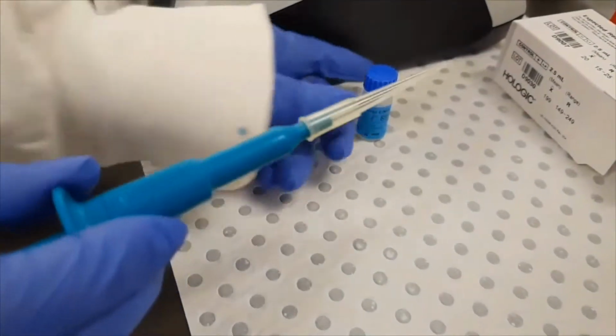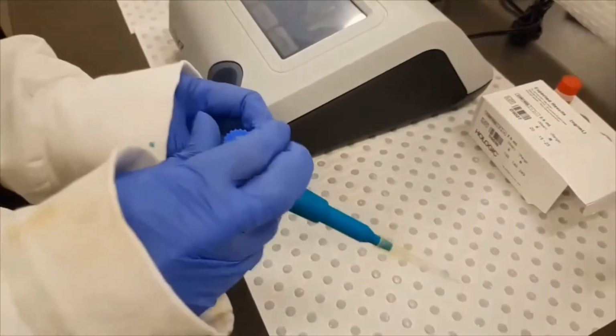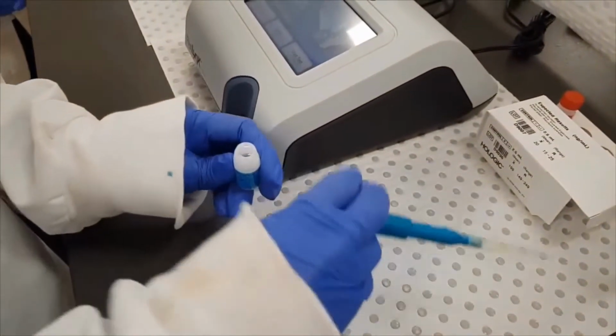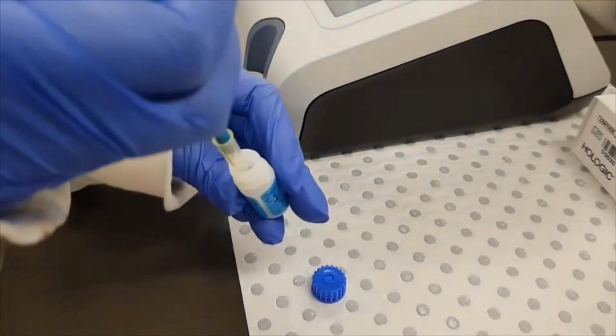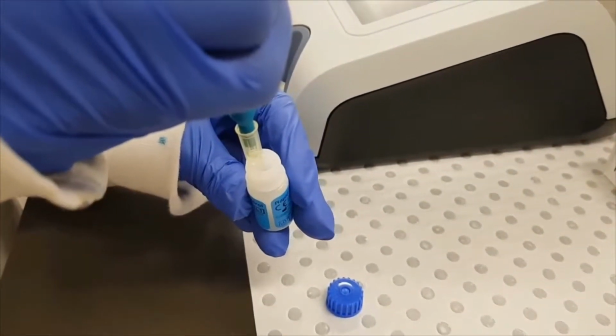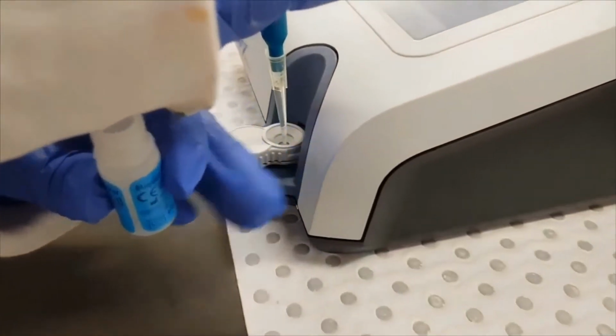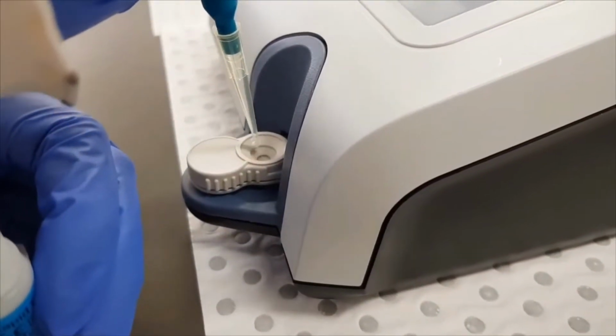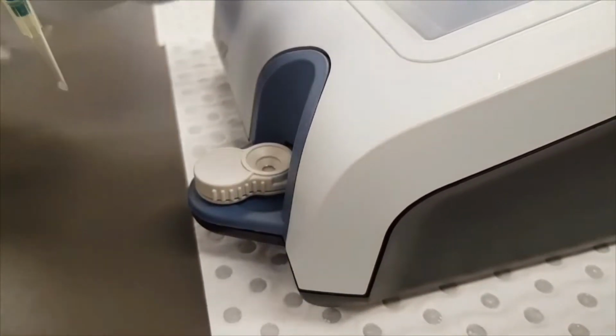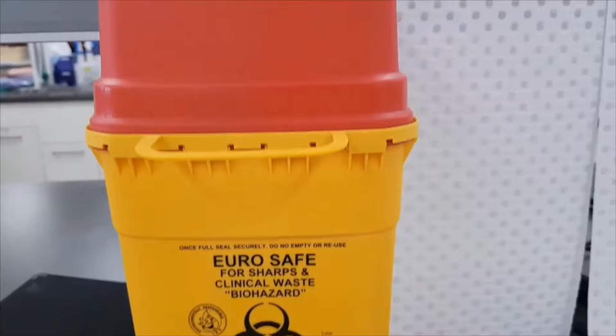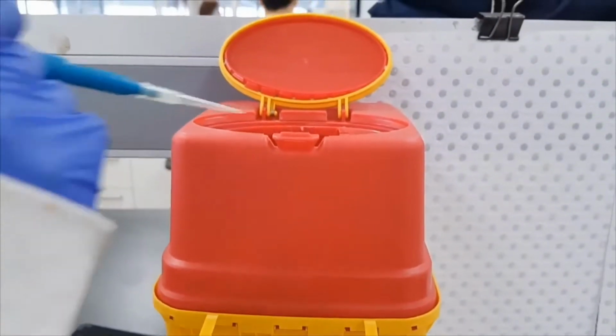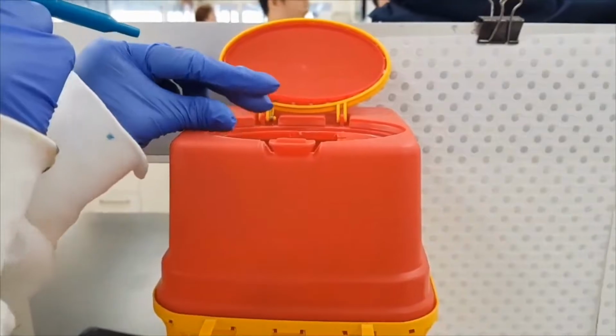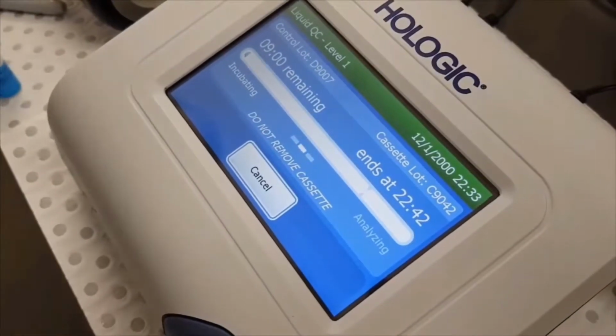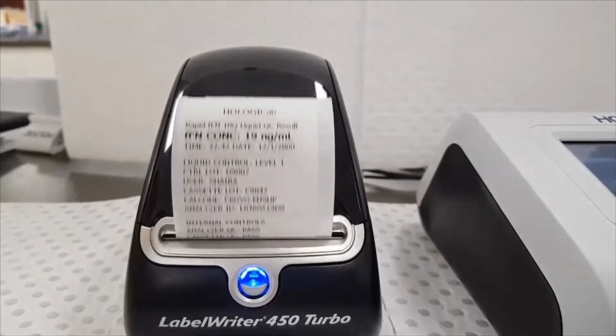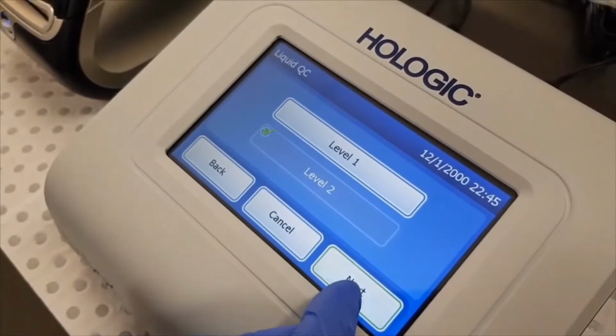With a pipette, attach the suitable tip. Slowly aspirate 200 microliters of the liquid from the bottle and place into the well of the cassette and start the test. Discard the tip into the sharps and clinical waste biohazard bin while the 10-minute analysis proceeds. Once level 1 passes, print results and finish to continue with level 2 control.